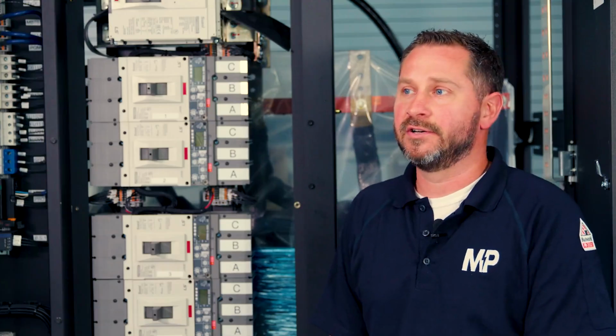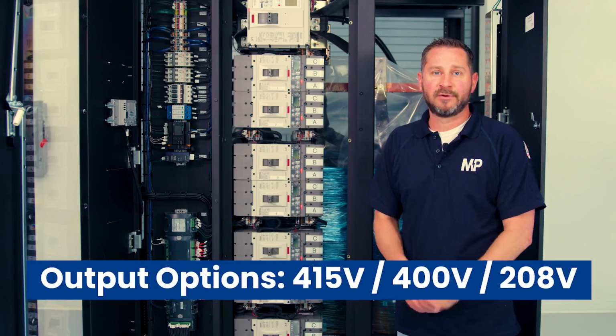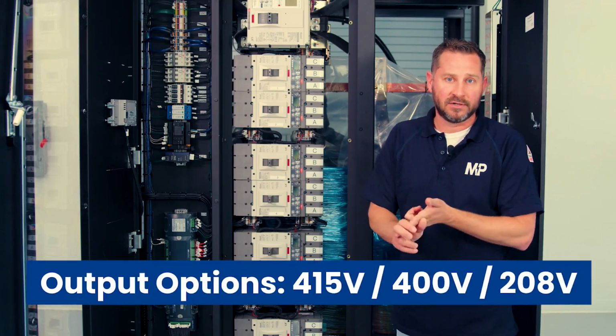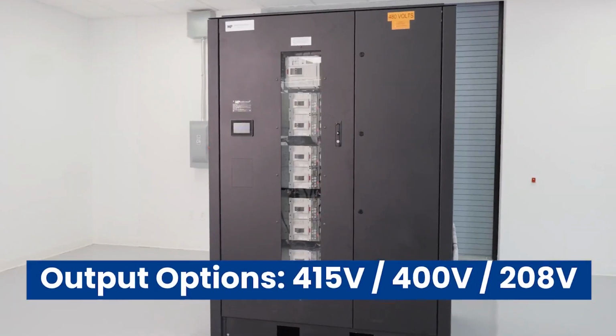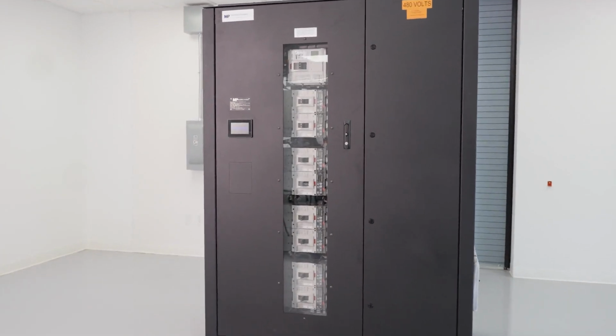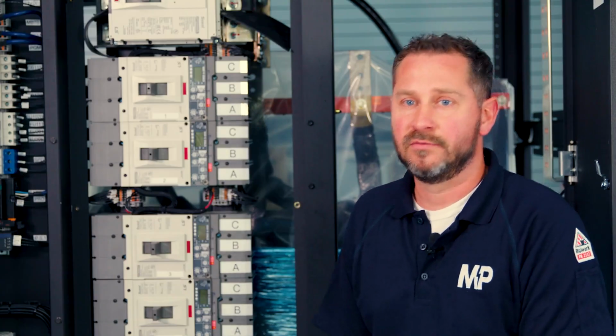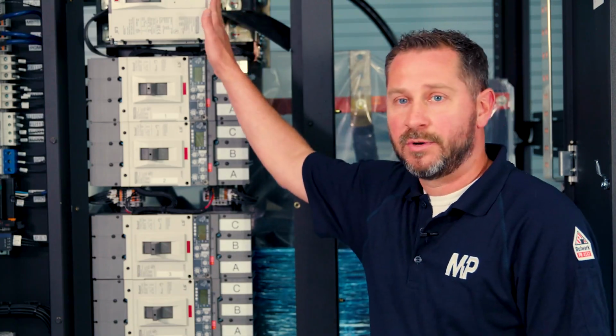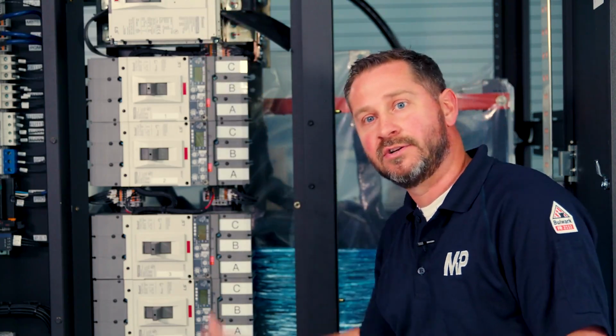This is a 500 kVA PDU. We have it tapped at 415. We can also tap it at 400 and 208. Right now, at 415, we're set at 696 amps. Our major components in this PDU, we have our main breaker on our primary side, followed by all of our feeder breakers on our secondary side.